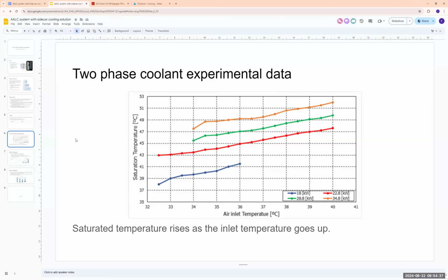But that I think is the point of this. Floor space is very, very important in the data center and expensive. So if you can get more cooling for the same physical space with a two-phase coolant than a single-phase coolant, then from a marketing perspective, that's a good reason to consider two-phase. But if the cooling capacity is identical, then I don't see the point of two-phase.